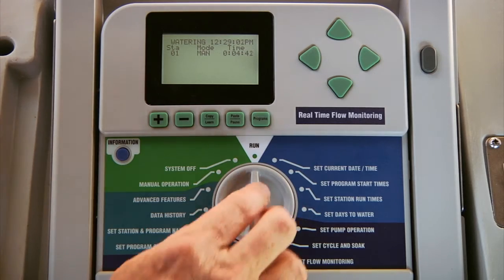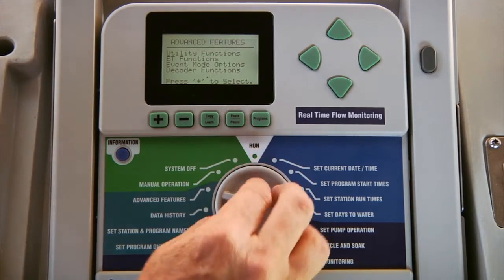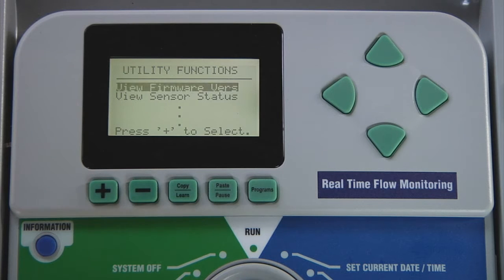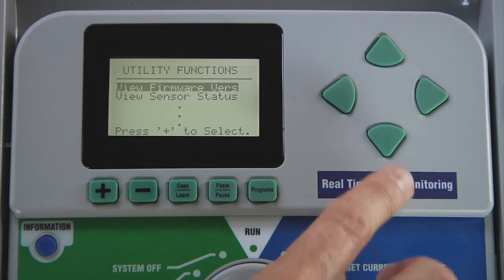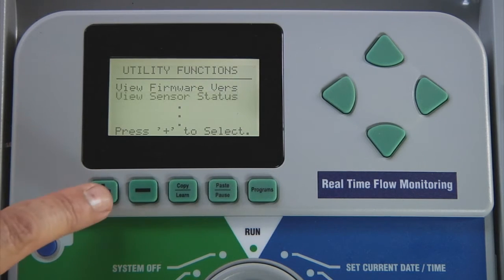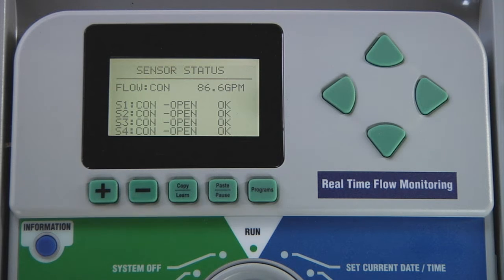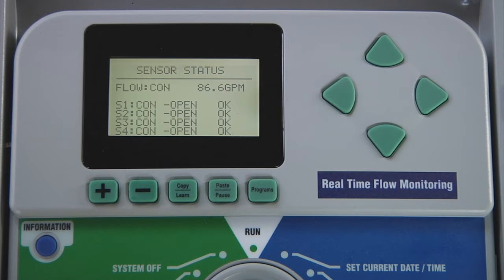To see real time flow, turn the dial to advanced features and select utility functions and choose view sensor status. This is the amount of water currently passing through the flow sensor. The flow value accounts for everything that causes the flow sensor paddle to spin, whether it is irrigation activated by the controller, an open hose bib, or a broken pipe.